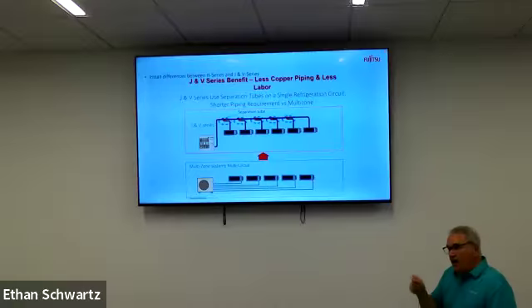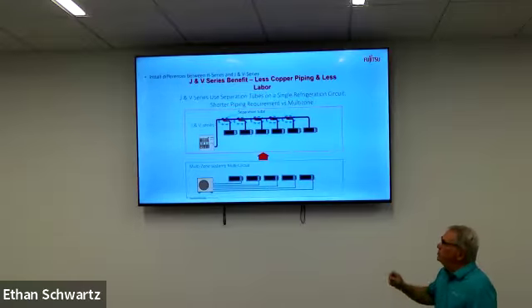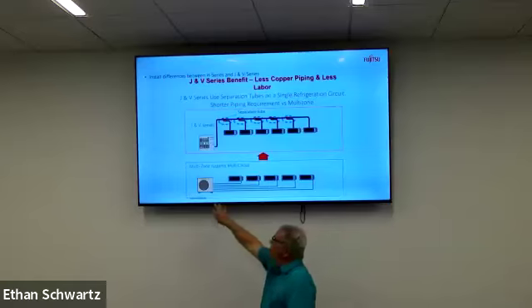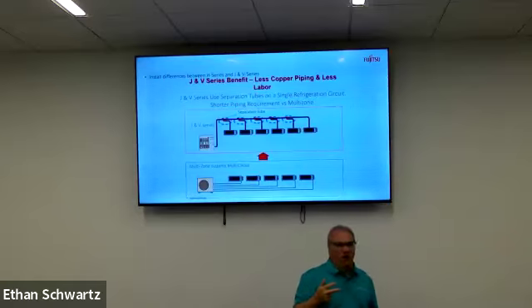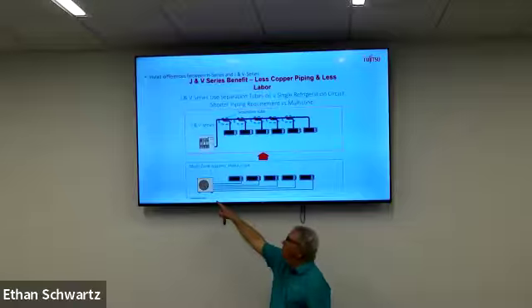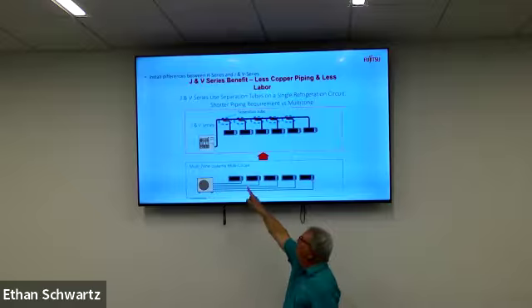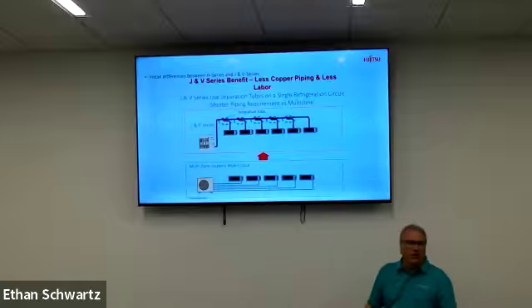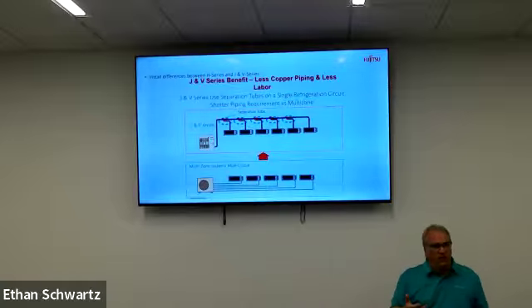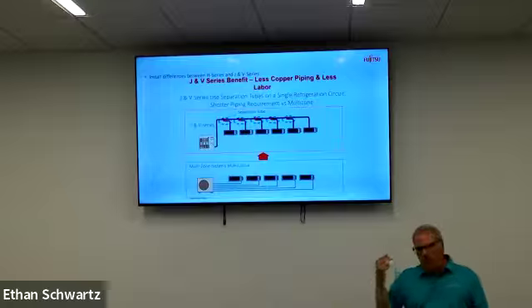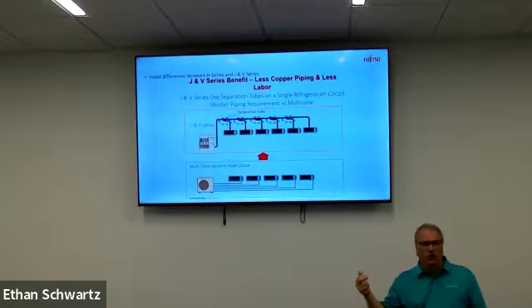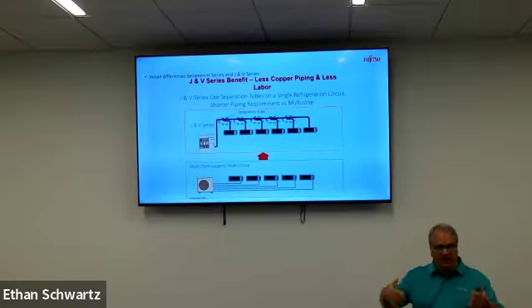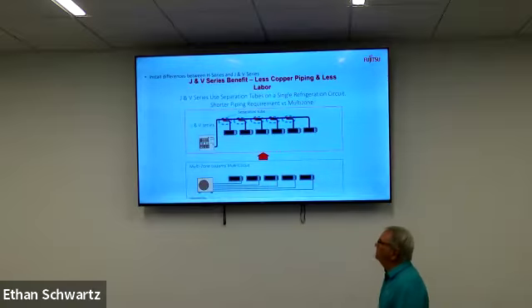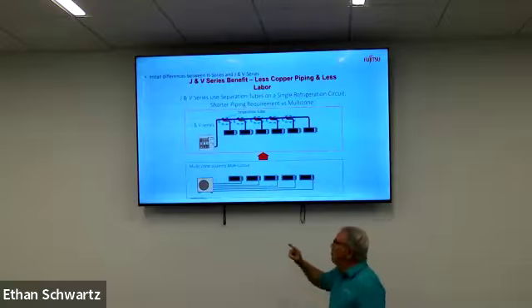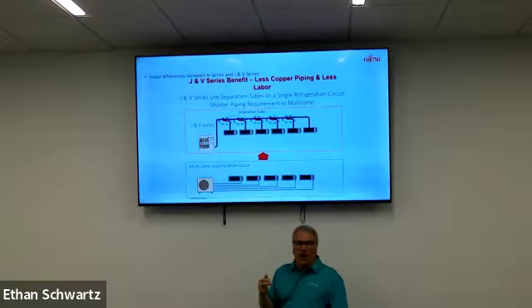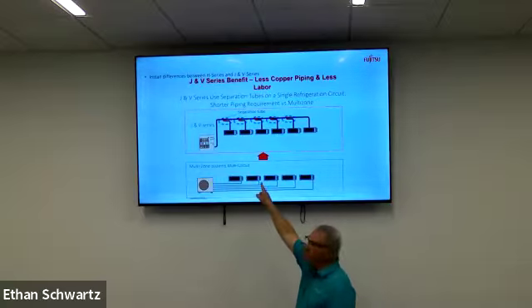And another thing as far as the installation. So this system would take one 2-pole breaker going to feed the outdoor unit, and then from the outdoor unit to each one of the indoor units is going to be the 3-conductor power line, as well as that control communication cable. Everybody familiar with how that feeds from there, because you sell the components, the cable that does that. So this installation only requires 2 circuit breaker spaces.